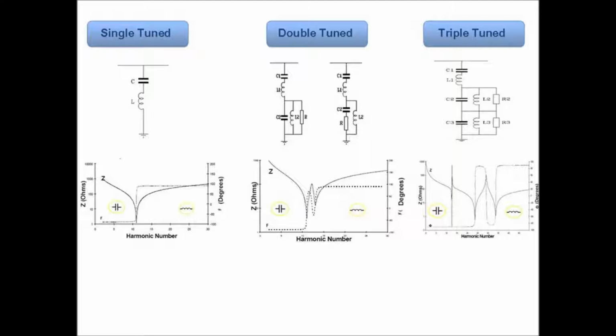And then triple tuned is a more elaborate form. It's worth noting that the single tuned does increase your losses at the 50 Hertz frequency. Double tuned not so much, and it is quite usable. Whereas the triple tuned also suffers from high losses at 50 Hertz and is more elaborate than the double tuned. So you tend not to see too many triple tuned filters out there.